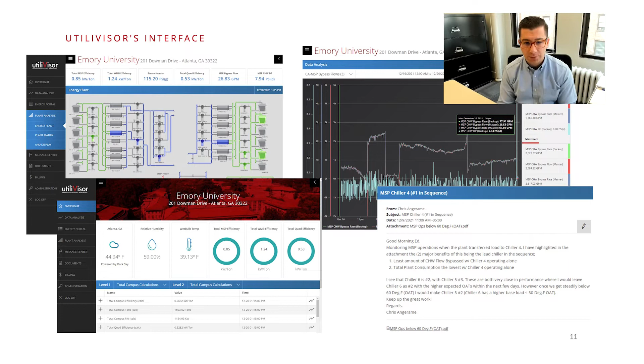Out of the three main chilled water loops, we focused on the standalone plant first, which was the Michael Street plant, because the other two plants had an interconnect and fed a lot more buildings, so we wanted to focus on somewhat of the simplistic system first. We were actually collecting a lot of data from the buildings connected to this chiller plant loop, as far as valve positions and actual individual flows to the buildings themselves.